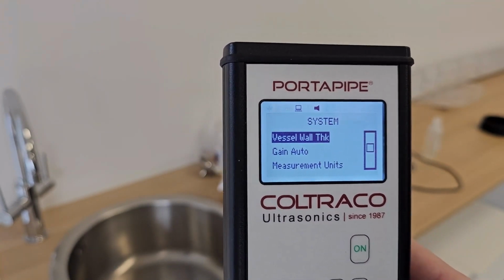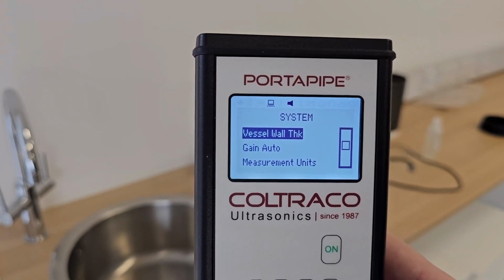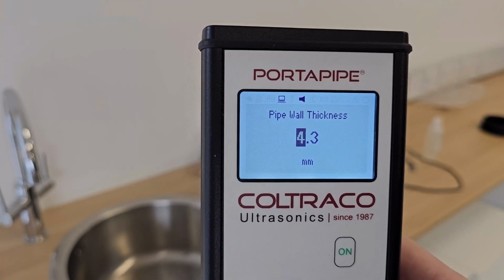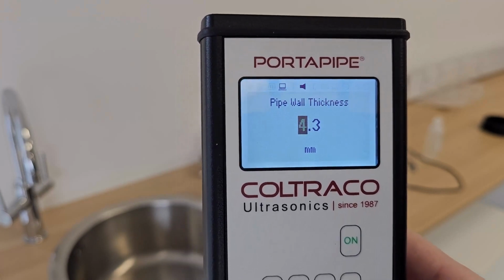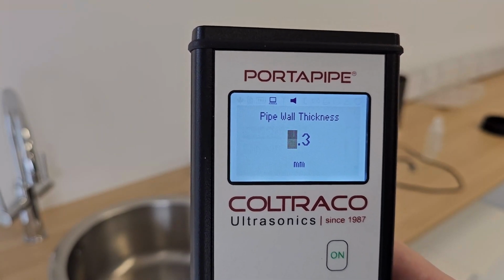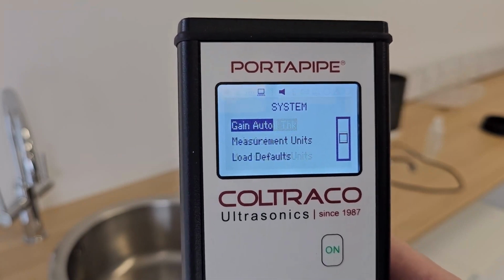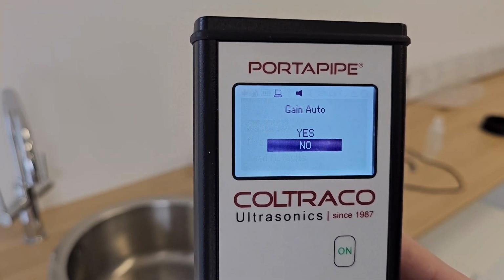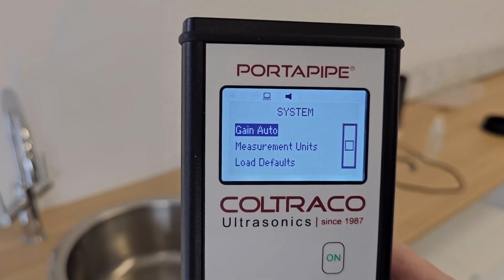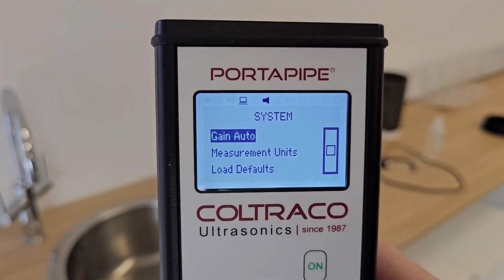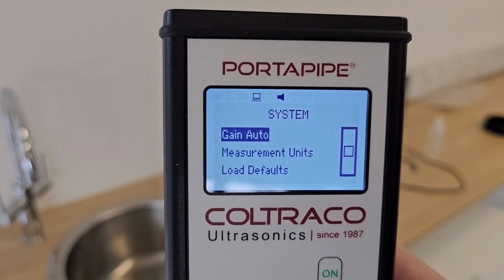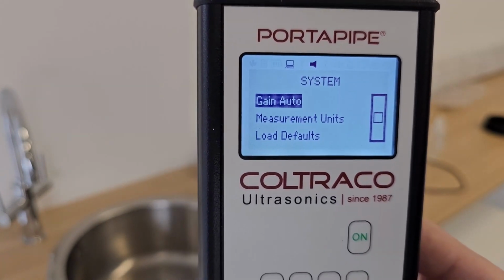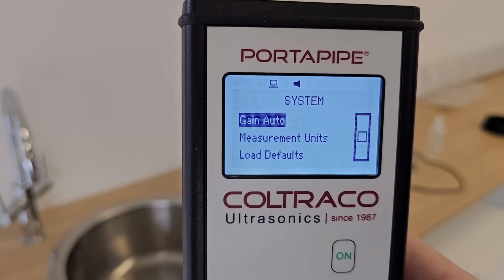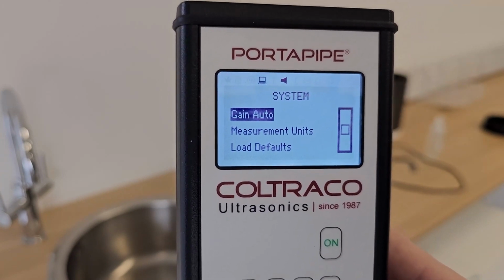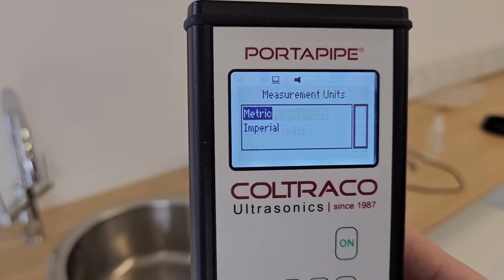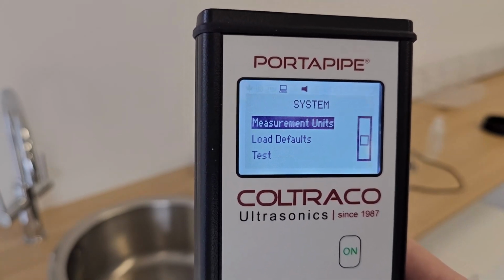And for the vessel wall thickness, I measured this before I started this video with the Porta Gauge 5 Coltraco Ultrasonics thickness gauge, and that was 4.3 millimeters. So I'll leave that as it is. We then got gain auto, and I've got this set to no, which means that the gain will not automatically adjust, and that's just because I'd like a bit more control so that I can demonstrate what happens as we change the gain. However, gain auto you may find a little easier for general use. And then we've got measurement units where we can switch between metric and imperial. I'll leave everything in metric for now.